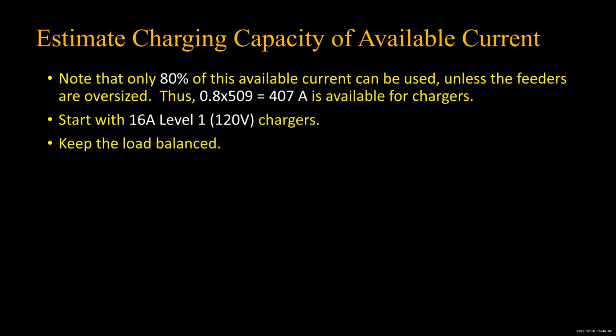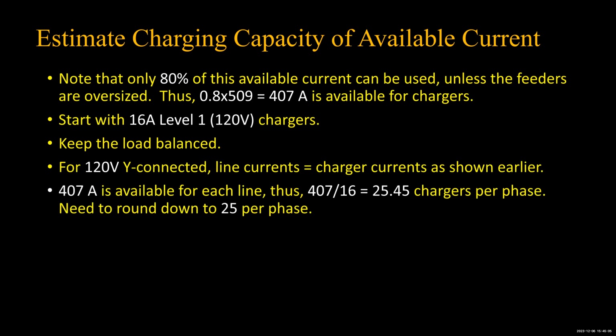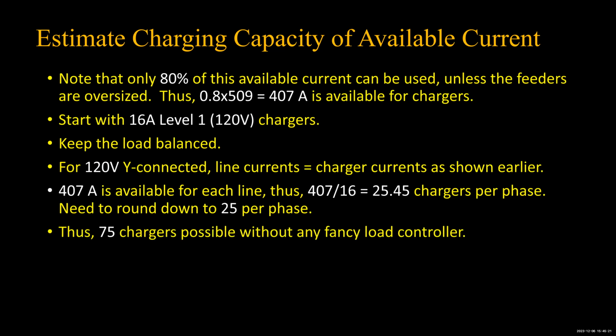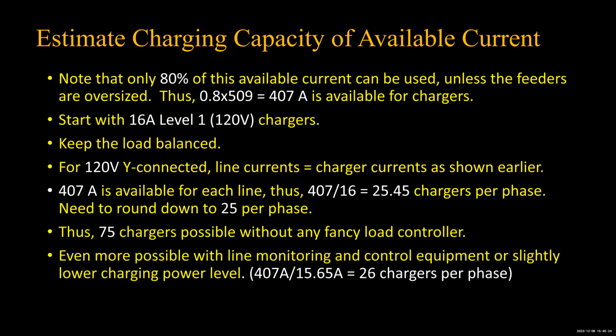Level 1, we know what we can do with that if we keep the load balanced. We can put 25 per phase, or 75 of those in there. And then we talk about whether we have to do the funny stuff with the 120 volt charging. Or we can say, now we're going to go with level 2. So let's see what we can do with that. If we take those 407 amps and divide by 15.65, monitor line current and stuff, then we could put 26 chargers per phase.